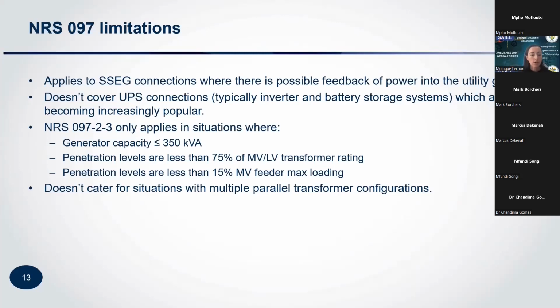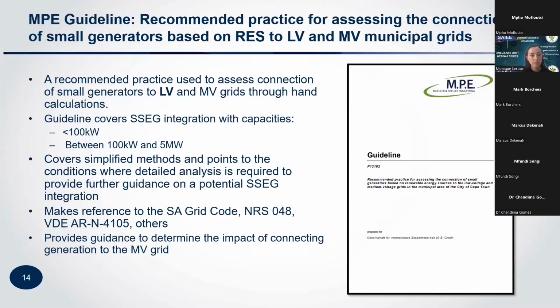And then NRS 097-2-3 only applies to generators with a capacity smaller than 350 kVA or where the penetration levels are less than 75% of the transformer rating or less than 15% of the maximum feeder loading. And it doesn't cater for parallel transformer configurations.